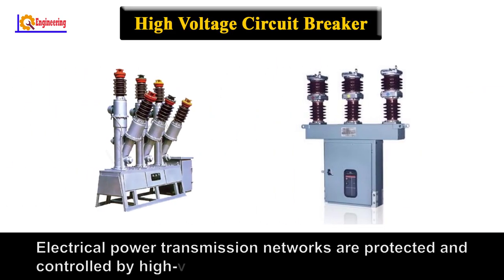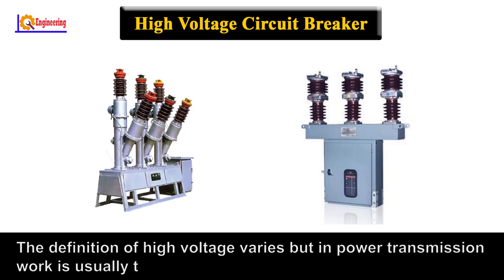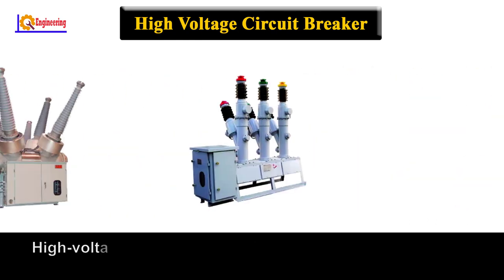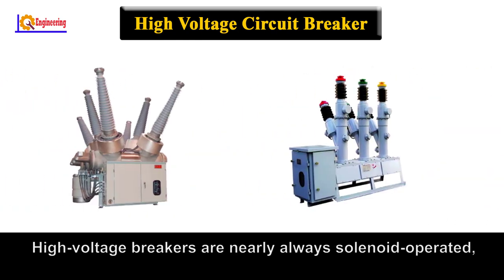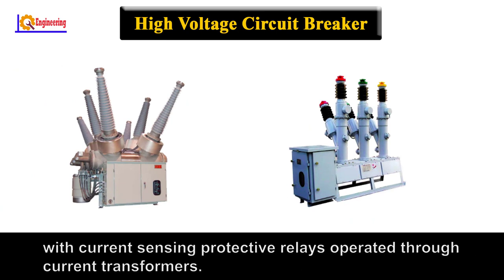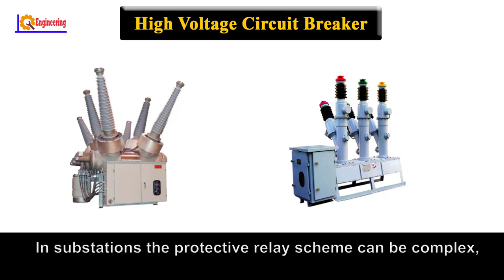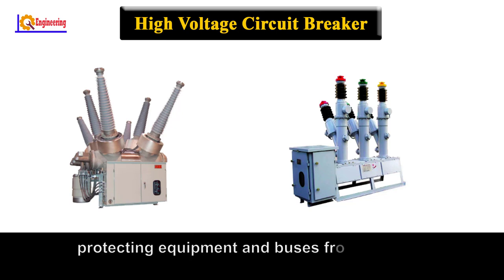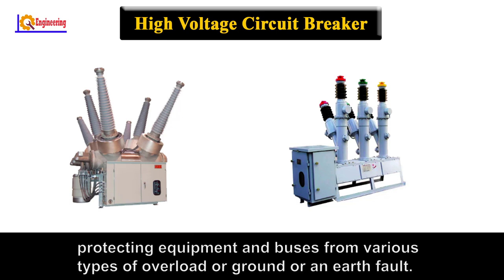High voltage circuit breaker. Electrical power transmission networks are protected and controlled by high voltage breakers. The definition of high voltage varies, but in power transmission work is usually thought to be 72.5 kV or higher. High voltage breakers are nearly always solenoid operated, with current sensing protective relays operated through current transformers. In a substation, the protective relay scheme can be complex, protecting equipment and buses from various types of overload, ground fault, or earth fault.